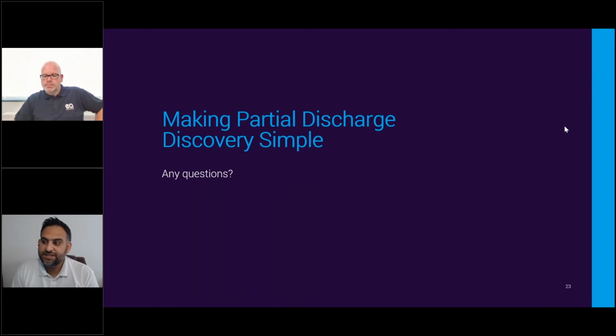What noise filtering techniques do we normally use for monitoring systems? So we have built-in algorithms that look at different types of partial discharge activity. It looks at noise filtration using artificial intelligence. There's also actual hardware noise cancelling as well. What we normally do is install some antennas around the monitoring system. We can pick up any external interference using those antennas, so we can differentiate between noise that is being imported from outside the switchgear and partial discharge activity that is being generated within the switchgear. So we can differentiate between noise and PD activity.